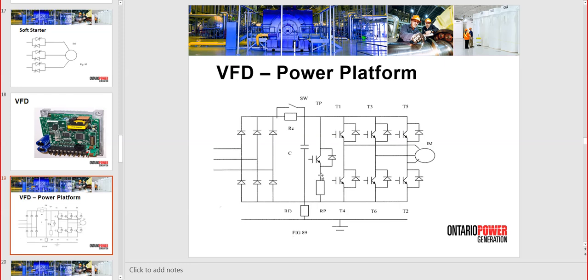Then you have a leg that is for braking. That is a resistor at the bottom with an IGBT and reverse diode, that is usually on the outside of the drive. It's called a dynamic braking resistor, and it can only take up to 15-20% of the power of the drive. You cannot have a full power resistor. Let's say the drive is a 50 kilowatt drive, you cannot have a 50 kilowatt resistor, but you will have a 10 kilowatt, maybe 8 or 10 kilowatts maximum. So this is a chopper.